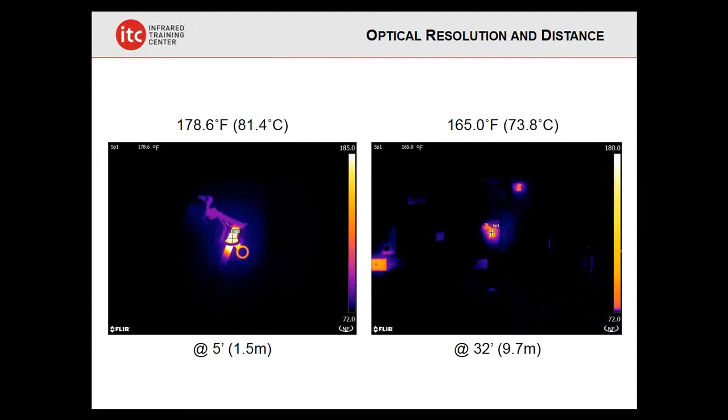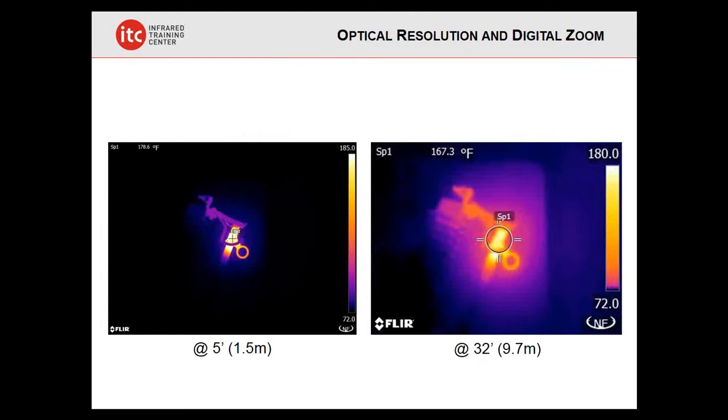If you notice there, we see a pretty significant temperature change. That's because the resolution has been affected by this distance. Now, the resolution is a fixed value, but now that they're further away, we're actually getting less detail. And with that, not good resolution on that temperature.